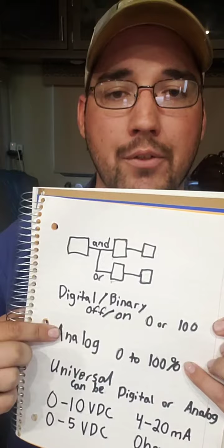Depending on what that value is, that's where it's tied into the logic. Written in the logic, it knows that if I have, say, 500 ohms on that thermistor, I'm just throwing a number out there, and that means I'm at 20 degrees Fahrenheit, right? Or a 10K resistor is, I think, pretty common. It's 10,000 ohms, I think, at 77 degrees, or depending on your type. And there are different types of thermistors out there.